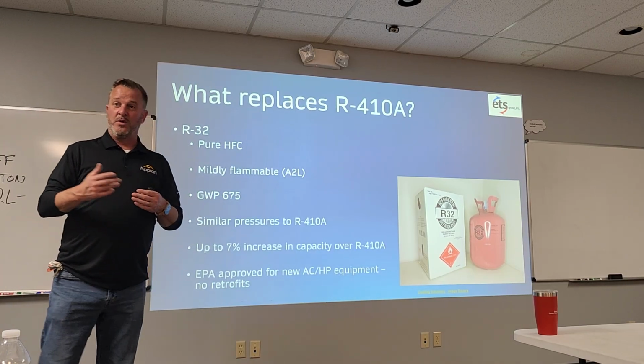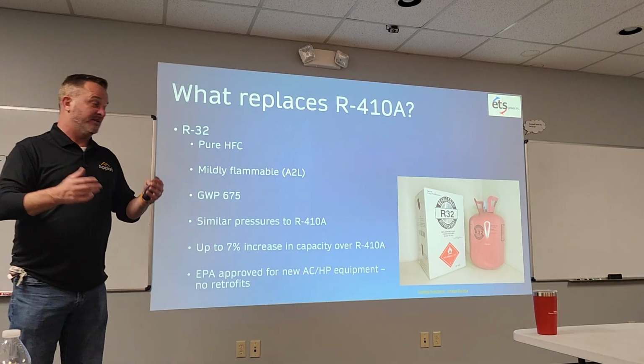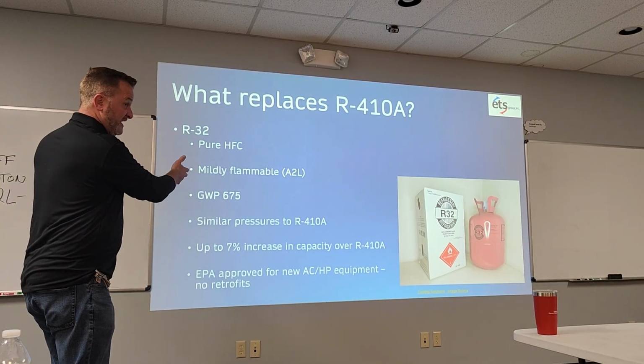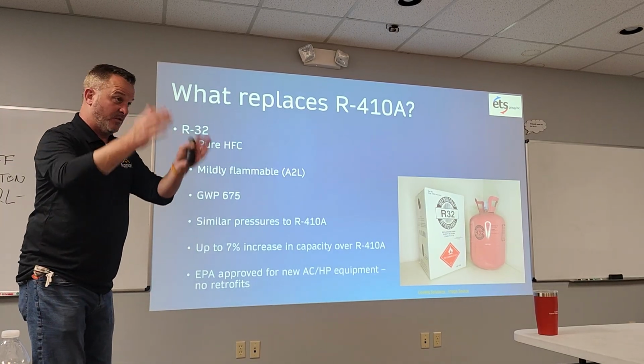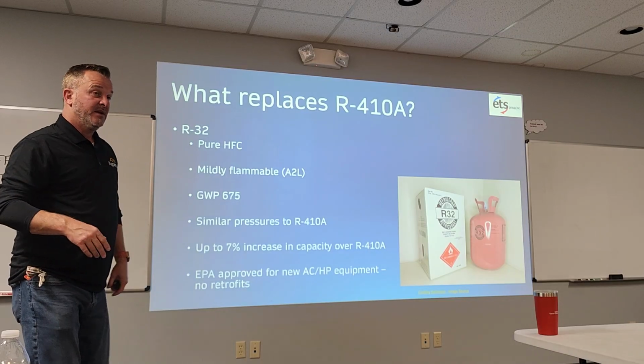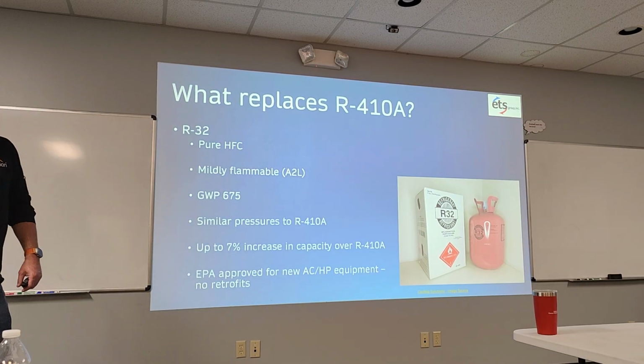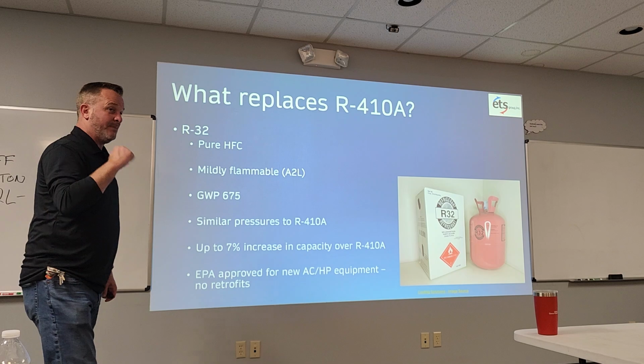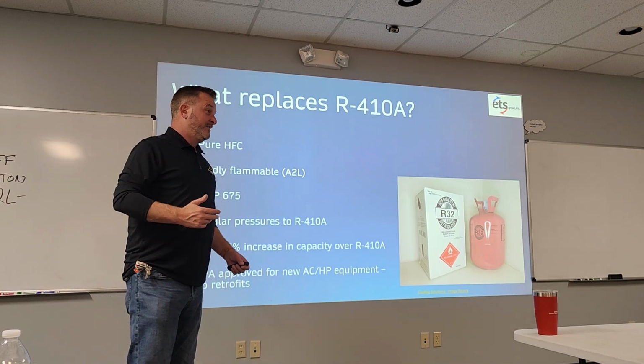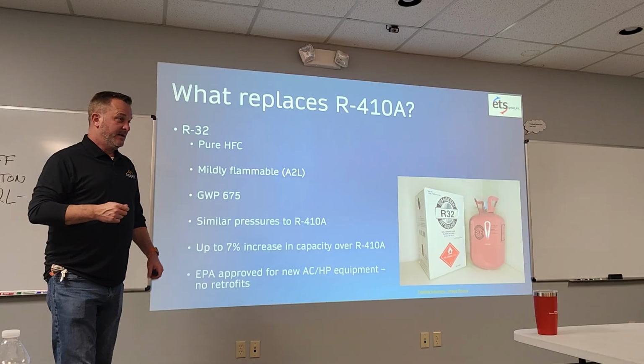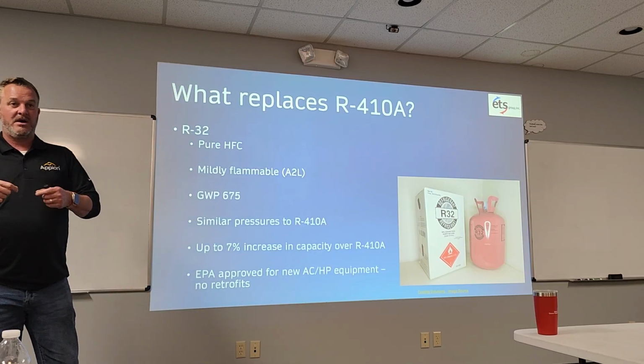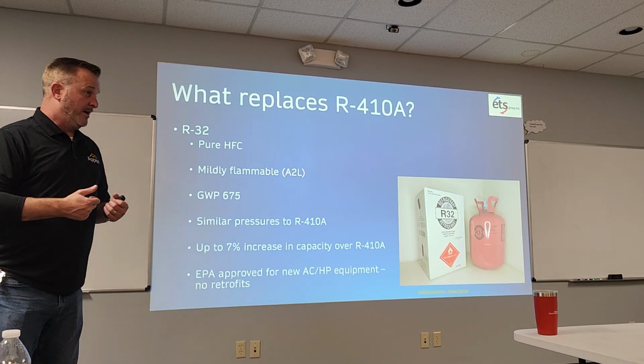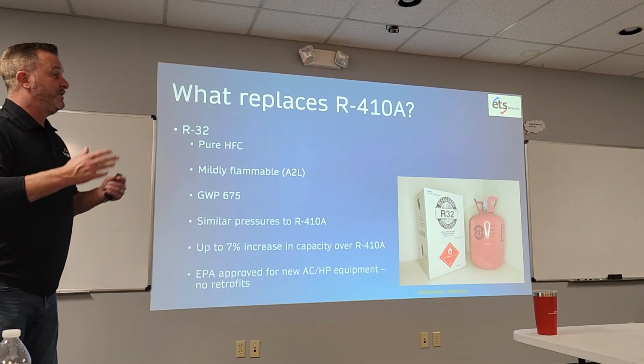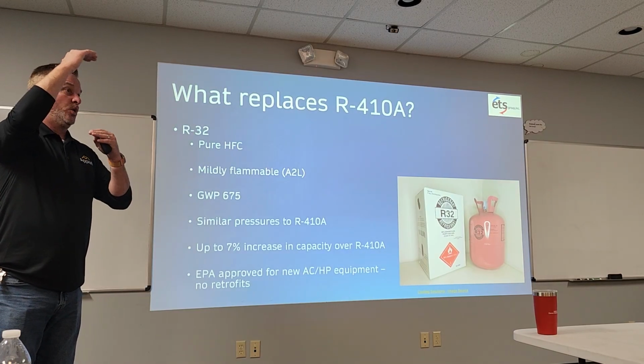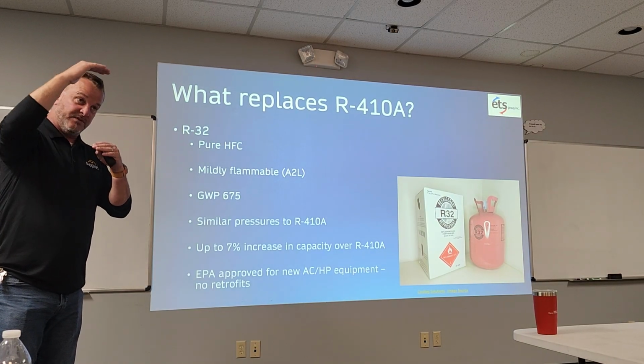We're not going to have that in this transition. They're not going to come out with a 410A replacement or anything else. It's going from 410A systems to R32 systems or 454B systems, that's it. So when we say top off, what does that mean? If I've got an R22 system and I want to top it off, how do I do it? With R22, right? Same thing with 410A, same thing with 134, anything. These replacements are not top offs or drop-ins, because they're mixed, they're two different refrigerants. Now you've got like 3 or 4 different refrigerants in there.